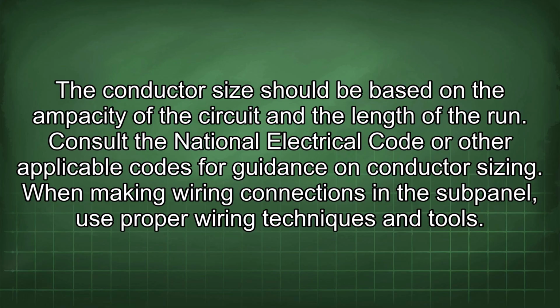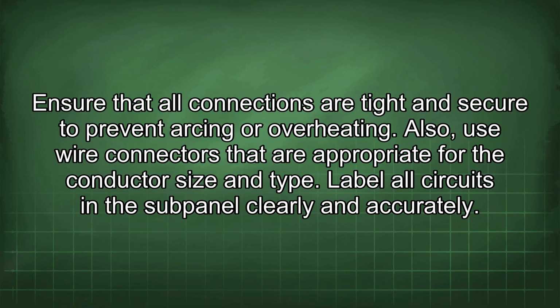When making wiring connections in the subpanel, use proper wiring techniques and tools. Ensure that all connections are tight and secure to prevent arcing or overheating. Also, use wire connectors that are appropriate for the conductor size and type.